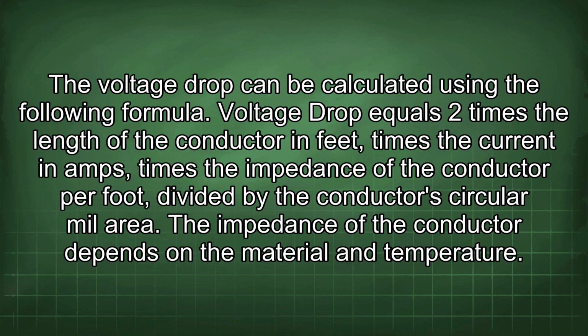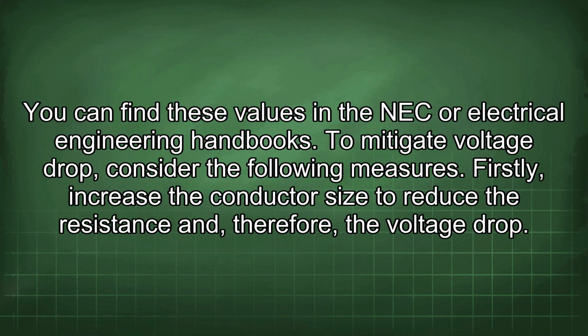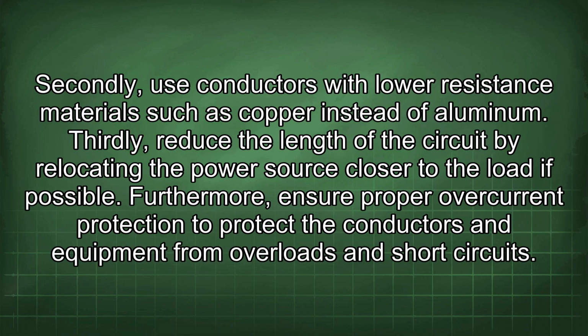Voltage drop equals 2 times the length of the conductor in feet times the current in amps times the impedance of the conductor per foot divided by the conductor's circular mil area. The impedance of the conductor depends on the material and temperature. You can find these values in the NEC or electrical engineering handbooks. To mitigate voltage drop, consider the following measures. Firstly, increase the conductor size to reduce the resistance and, therefore, the voltage drop. Secondly, use conductors with lower resistance materials such as copper instead of aluminum. Thirdly, reduce the length of the circuit by relocating the power source closer to the load if possible.